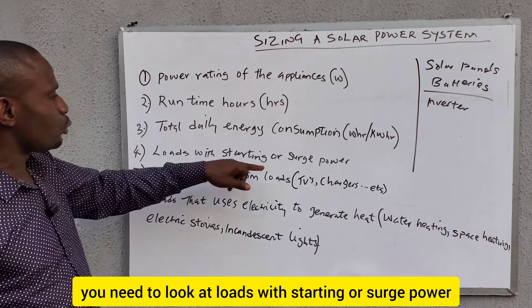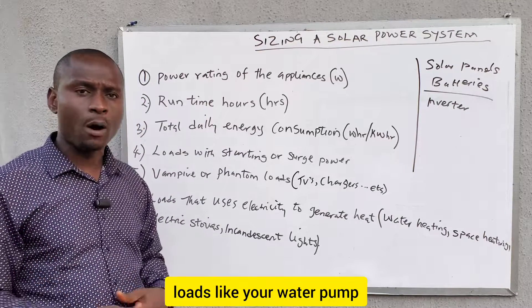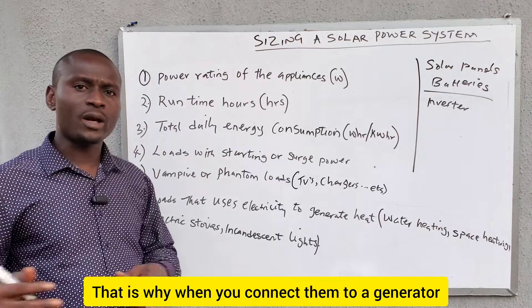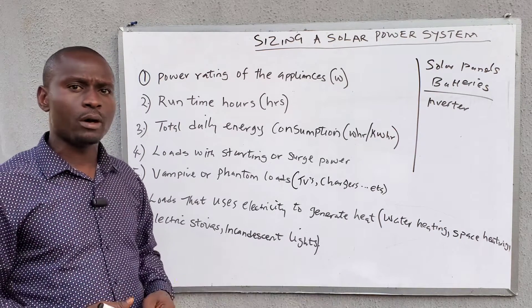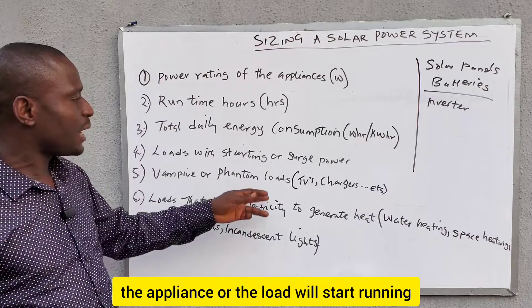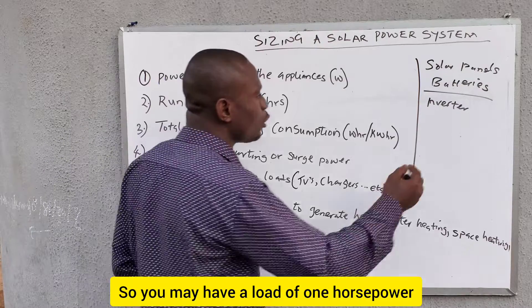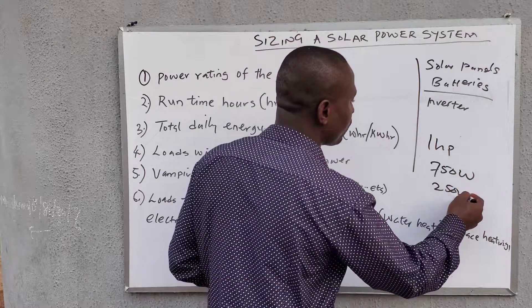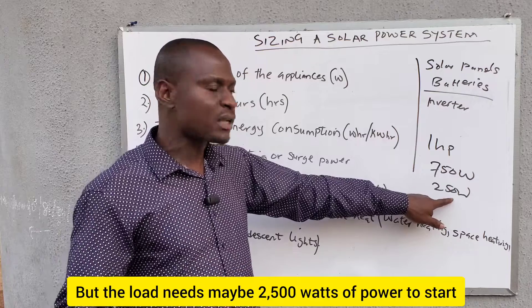You also need to look at loads with starting or surge power. Loads like water pumps, AC water pumps, refrigerators, and air conditioners have starting power. When you connect them to a generator and switch them on, the generator sounds heavily loaded for a few seconds, then the appliance runs at its normal power. For example, a one-horsepower load — 750 watts — may require 2,500 watts of starting power. That surge lasts just about five seconds before it returns to its normal 750 watts. We call this starting power or surge power.